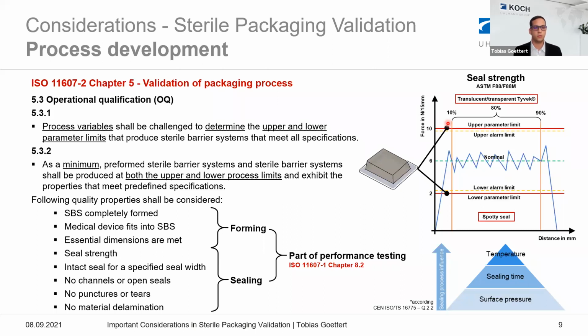And therefore you have to define your parameters. They correspond to your sealing parameters: the temperature, sealing time, and pressure. And it's very time intensive, but you have to define the upper and lower limits, because the standard ISO 11607-2 also says you have to at least test your worst case configuration. What does worst case configuration mean? It means you have to test your samples from both the upper and lower limit.